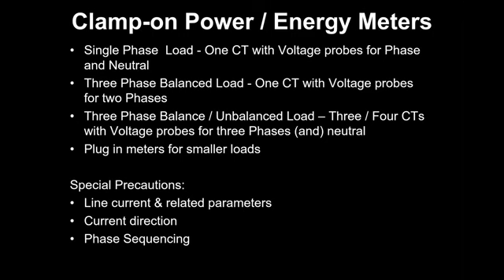A plug-in meter can also be made. We had got it made ourselves earlier for a certain application, because for industrial sockets, you don't have plug-in meters. At least I am not aware of any. So we made a board with an energy meter and an industrial socket, and then the cable connects. Whatever the cable is, it will come to the board through the meter, and through this it gets connected to the industrial socket or normal socket. So depending on whatever socket is there for that load, we used to connect it through our board and do the measurement. So this is basically for smaller loads.